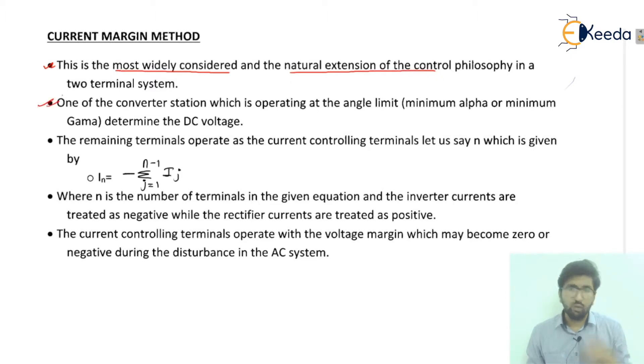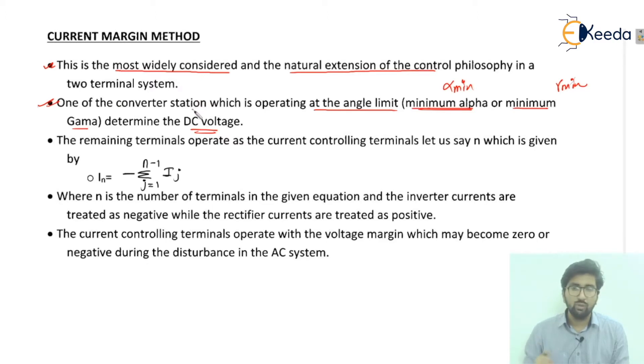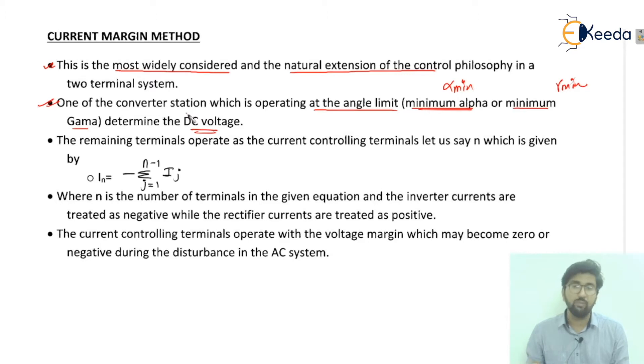One of the converter stations operating at an angle limit determines the DC voltage. The angle limit refers to the minimum alpha (alpha minimum) or the minimum gamma (gamma minimum). If we are talking about the rectifier, it operates at alpha minimum for DC voltage determination. If we are considering the inverter, it operates at gamma minimum to determine the DC voltage value.